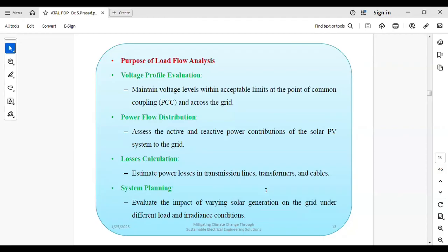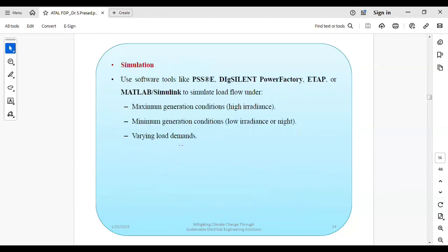Because sometimes, because of clouds, your generation will get reduced. So that case study also you need to perform. That means when the generation is very, very low, what will be the effect produced in the system when the plant is connected to the grid. So those are the different case studies: maximum generation condition, minimum generation condition, varying load demand. If the load changes for different operating scenarios, you have to conduct load flow analysis. Then for maximum generation condition, 100% generation, and suppose you are looking at 10% generation, 25% generation, different generation levels, you have to perform the load flow analysis.